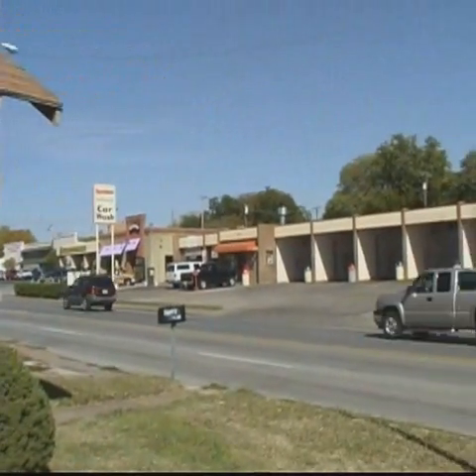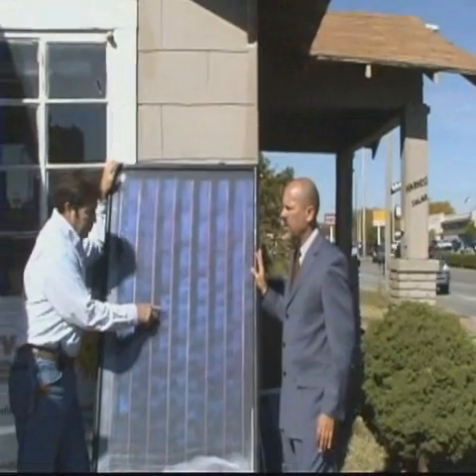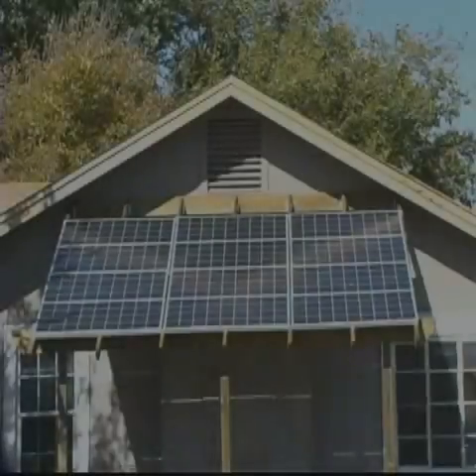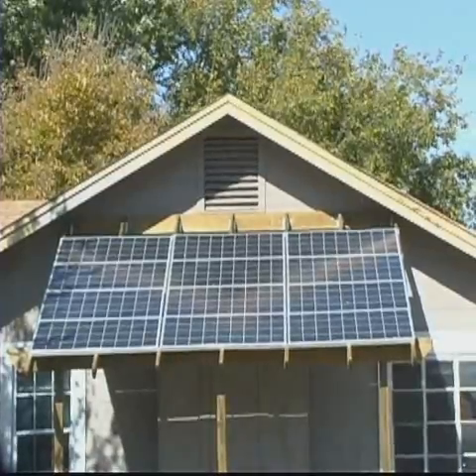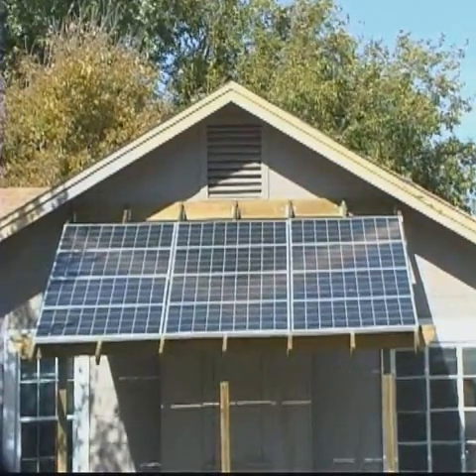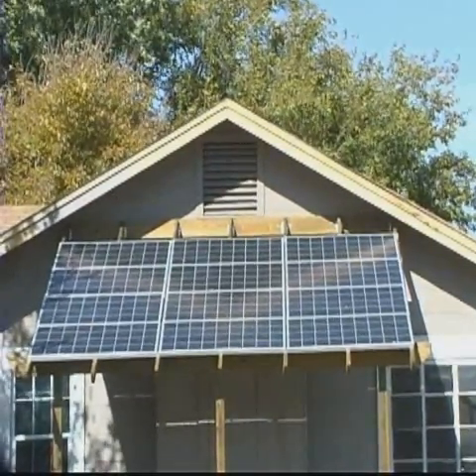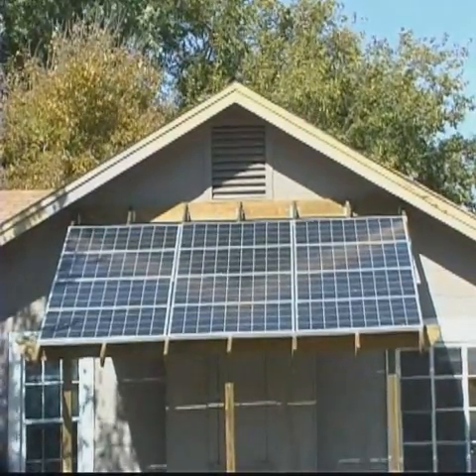This panel — let me tell you a little bit about it. It's from Germany. It's T-I-N-O-X, the TINOX panel. It is the most efficient panel in the world. It's bright blue with copper risers, and the water goes in at the bottom, rises up through these, collects that solar heat, and comes out of the top. If I hooked this up right now, it would scald you coming out — one pass turns it to 130 degrees. We have a dedicated canopy providing 1,500 watts of solar electric photovoltaics, which will produce 10 kilowatt hours a day on an average day — more in summer, a little less in winter. That feeds directly into the grid and offsets your power requirement.